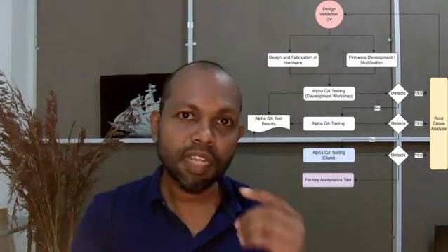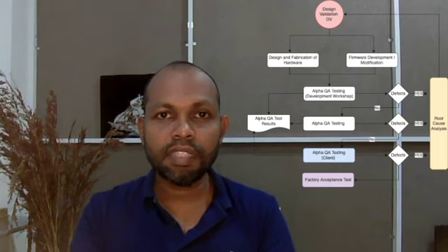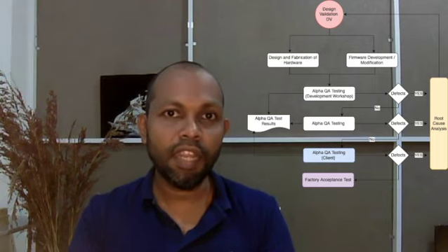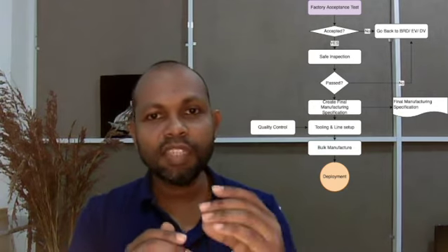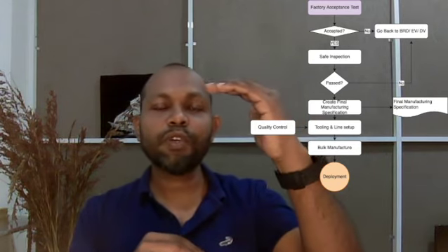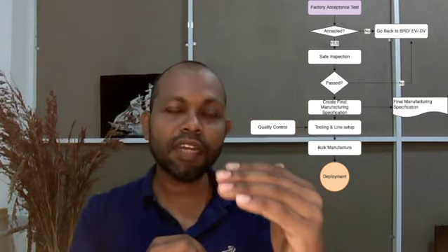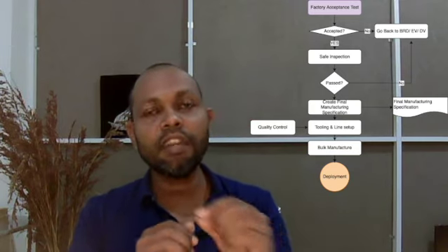So we test and verify each and every step to make sure that the design is within certain failure limits to match the hazard risk analysis we did previously. So all these things take a lot of time, and after everything we do a verification validation phase where we verify that all these business requirement documents, design requirement documents, architecture, specifications, hazard risk, everything is tested and verified.